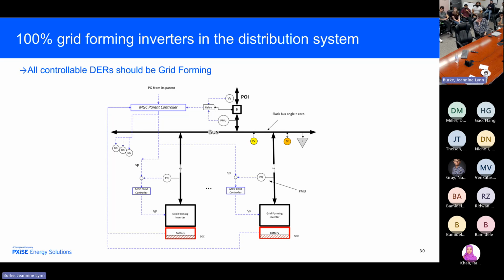If my frequency here is at 60 hertz, guess what? My angle is constant. That means the angle difference between here and here is constant. That means the flow here is constant. So I have achieved my objective of controlling the flow at this point with the same controller that I use here and there and all the way up the grid. One piece of software that does everything we just talked about.